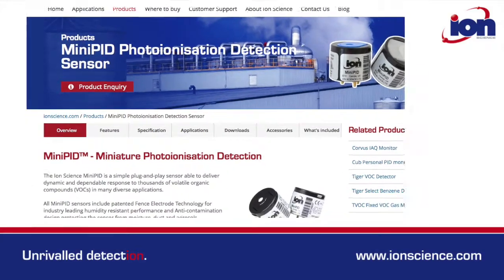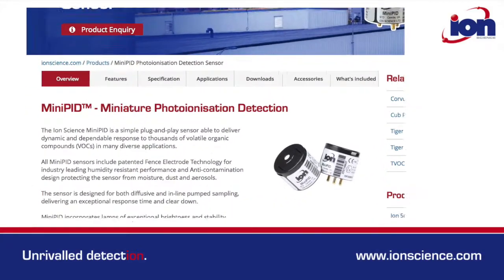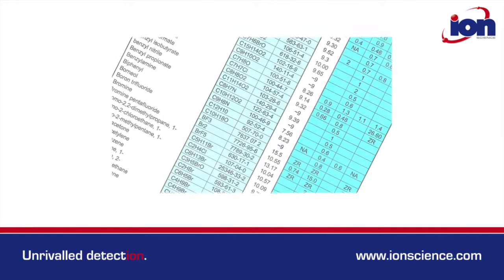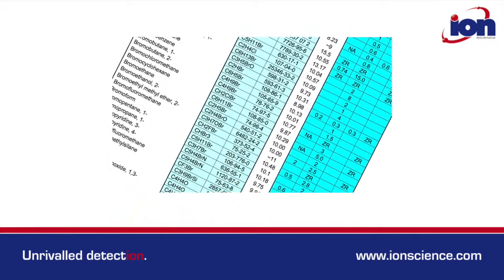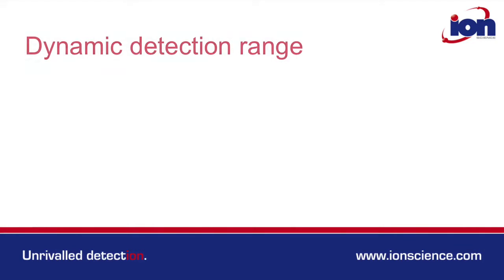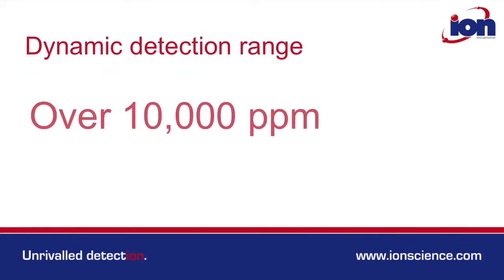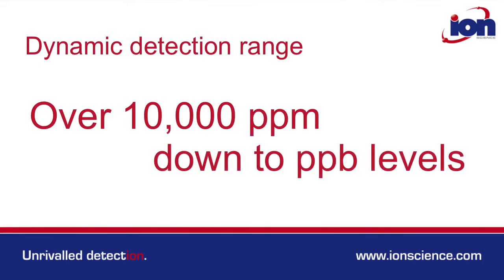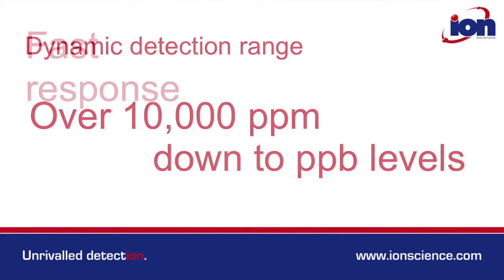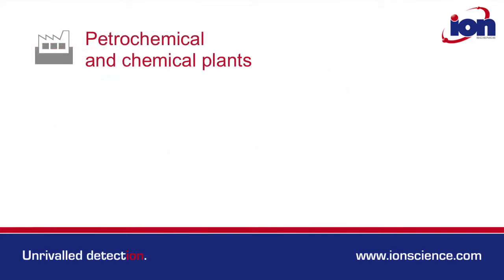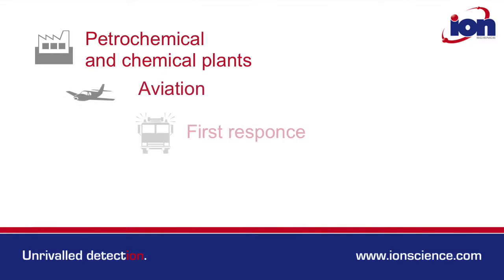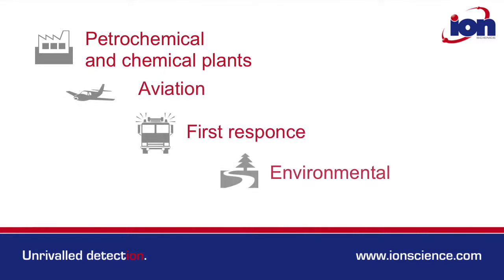PID is a great gas detection technology. It can detect hundreds of volatile organic compound gases. It has a dynamic detection range from many thousands of parts per million down to parts per billion levels, and it also boasts a fast response time. All this makes PID an ideal gas detection technology for a wide range of applications.